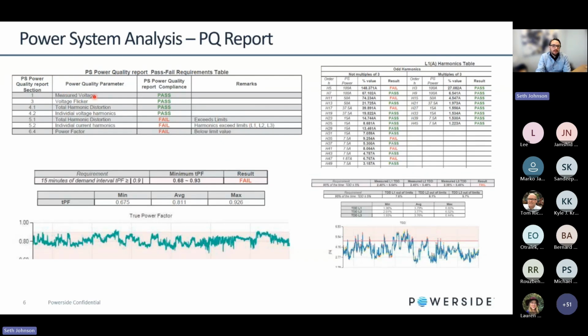So from a high level, we're looking at voltage, flicker, total harmonic distortion, individual harmonics, total harmonic distortion for voltage, as well as individual harmonics for voltage, and then of course power factor. One of the reasons why we focus on this, of course, is because from a solutions portfolio standpoint, we primarily play in the power factor correction as well as harmonic mitigation solutions. So most of the time when we're sending out this product to do a power systems analysis, it's because the client believes they're suffering from either a harmonics related issue, or they need to maintain a specific power factor and they're not quite sure what it is.